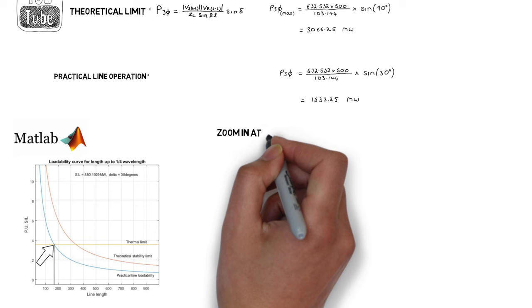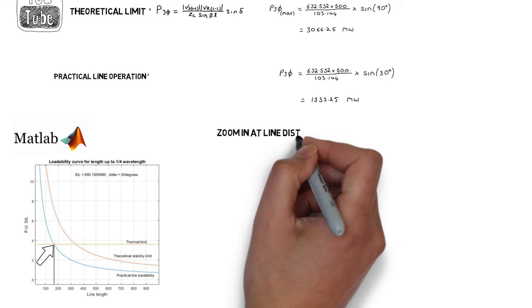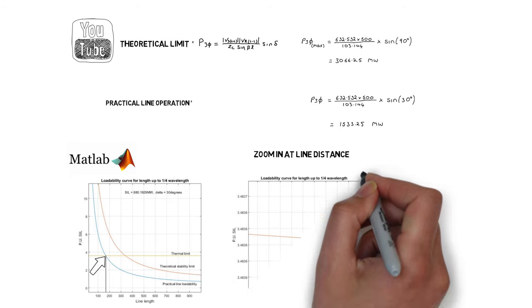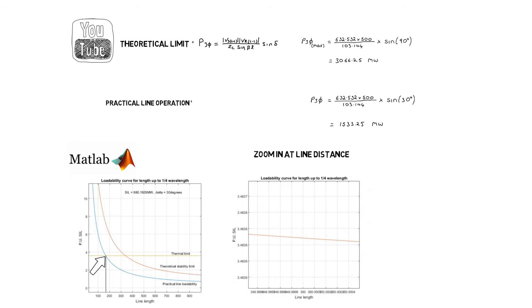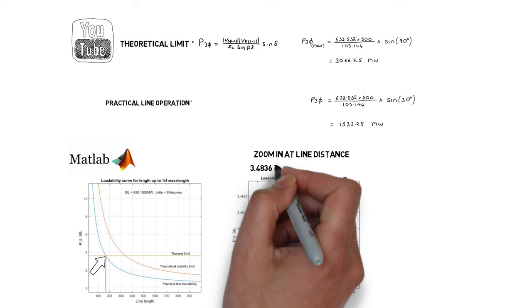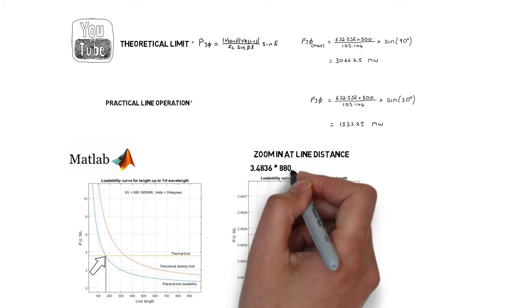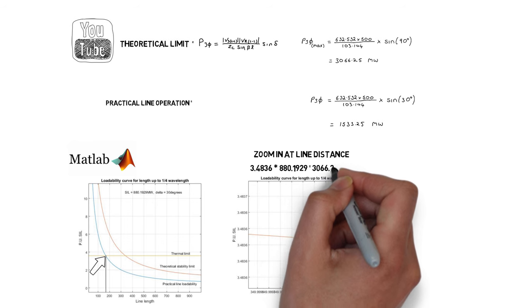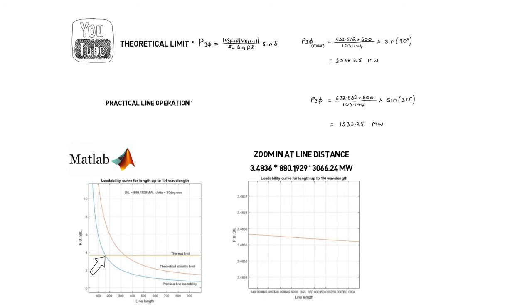To verify the exact values for the theoretical limit I will zoom in at the distance of the line. In this example a line length of 350 kilometers was used. This is equal to 3.4836 times the SIL and is equal to 3066.24 megawatts.